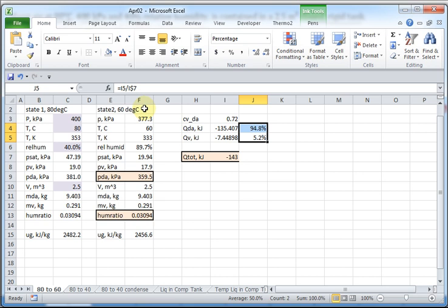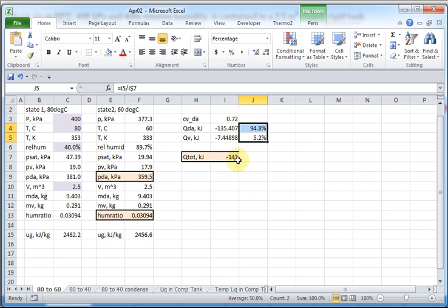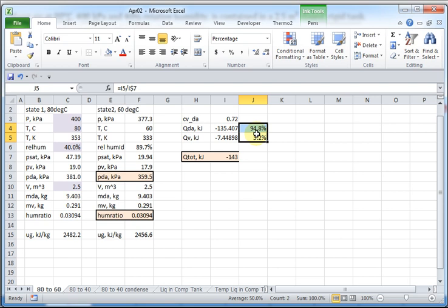And you can look up the values of uf and ug at the different temperatures. Use specific heat for the dry air. Calculate how much it takes to cool the dry air, how much it takes to cool the water vapor. Because there's so much less water vapor, it's a lower amount. And it's 143 kilojoules needs to be removed of heat transfer. 95 percent of that is to cool the dry air. And about 5 percent of it is to cool the moisture. Now, it is a small amount to cool the moisture. But humidity ratio is about 3 percent. So, it's only 3 kilograms of vapor per kilogram of dry air. So, this looks all about right.